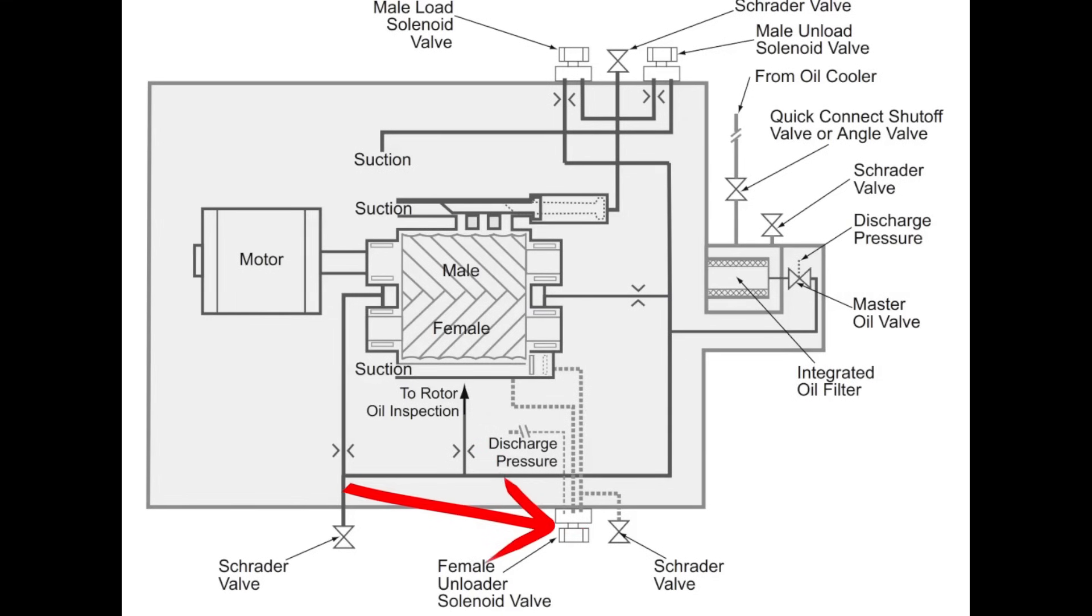When it engages, that is closing this bypass to where now we have full flow through the compressor. We're no longer going back into the suction from discharge. And having a hot gas bypass is basically what's happening here. We do this at startup to minimize the load on the compressor and allow our EXV to open and start feeding the evaporator in a timely manner.